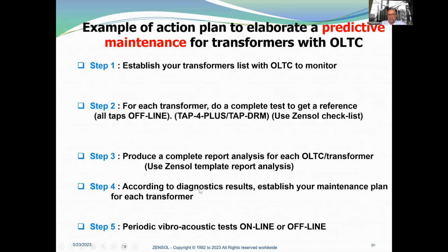Step 4, according to the diagnosis results, you can establish your maintenance plan for each transformer, because at this time you have a lot of information on your tap changers and your transformers, whether they work properly or not. When you are able to do step 3 properly, you know exactly how your tap changers are operating and if they work correctly or not. And step 5, after that you can do a vibro-acoustic test online or offline only, without the DRM. The DRM has been used just to help you understand the vibro-acoustic and when the impact is occurring at the time of the transition of the tap.